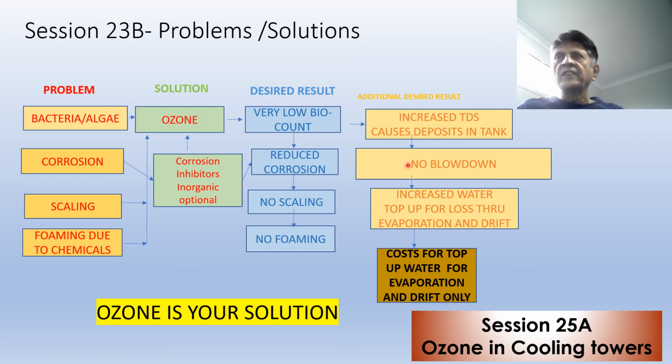But if you have a high TDS because of the chlorine differences, then blowdown will be required. Whether it is ozone or chemicals, you have to reduce the blowdown to reduce the chloride content to much below 300 ppm. Remember, even the 300 ppm of chloride in the water will have some detrimental effect on corrosion because of the electrolytic reactions.